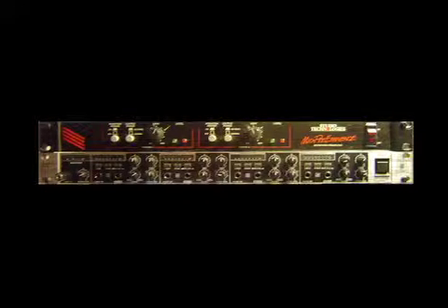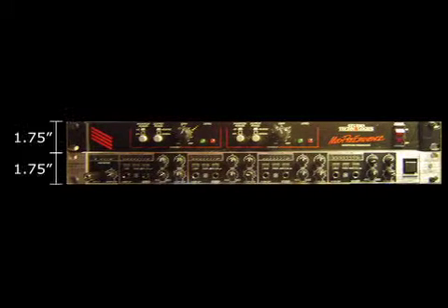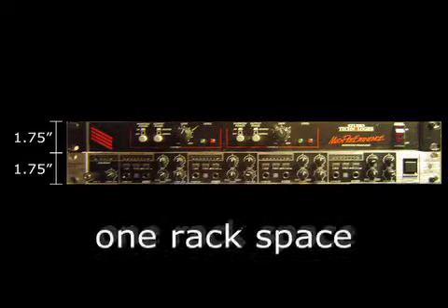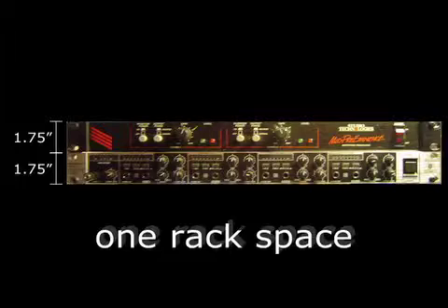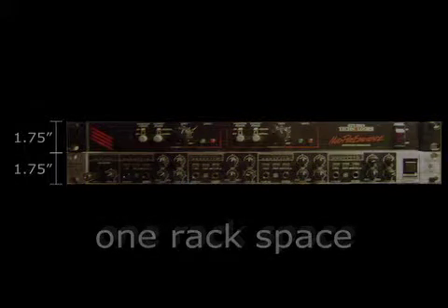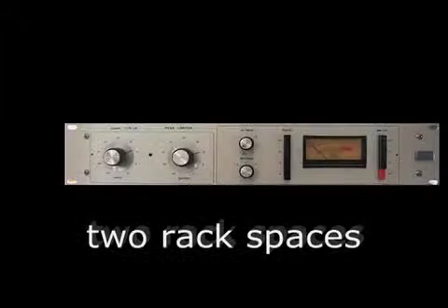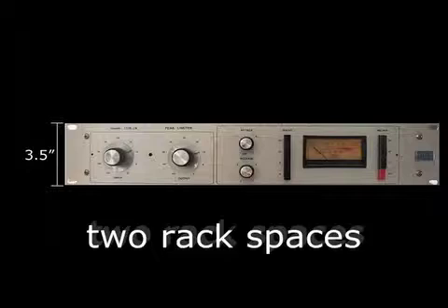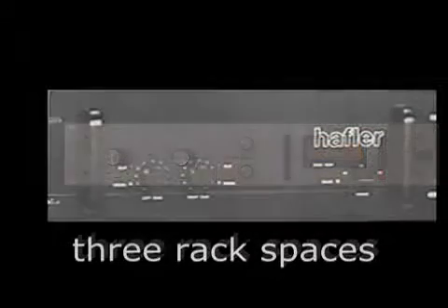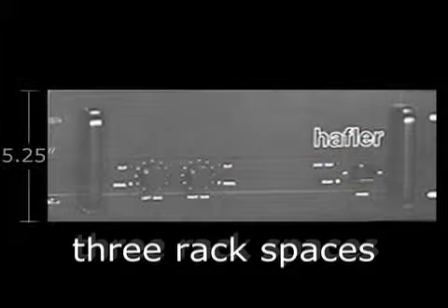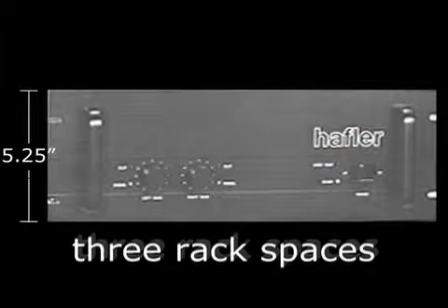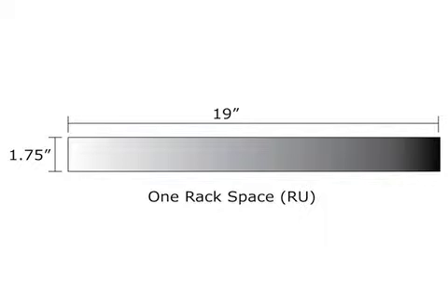The height of a single rack unit is 1 3/4 inches, also known as one rack space. A one rack space piece of gear is this height. A two rack space piece of equipment is 3 1/2 inches high. A three rack space piece of equipment is 5 1/4 inches high—all multiples of 1 3/4 inches.